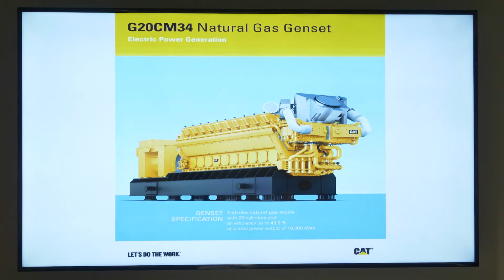So this is what the 20-cylinder engine looks like - it's 720 RPM, 4-stroke, 20-cylinder. We're pushing almost 49% efficiency on this unit. In this market, the 10 megawatt machine, we really only have one viable competitor: Wärtsilä. That engine is made in Finland, and they've been in this marketplace a lot longer than our medium speed engine. But you'll find from a technical standpoint, the two engines are pretty equal.